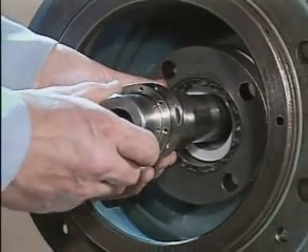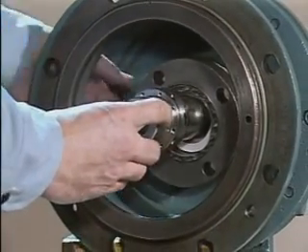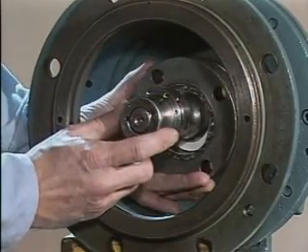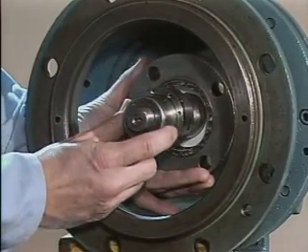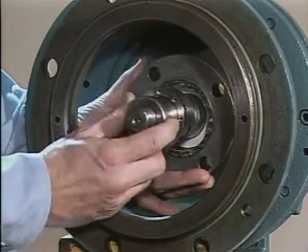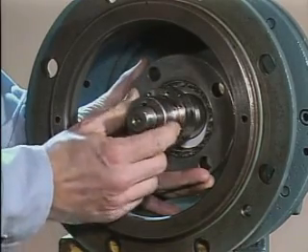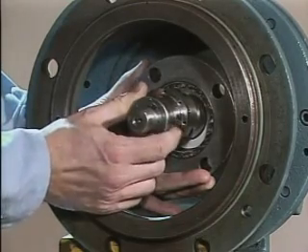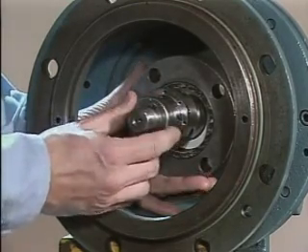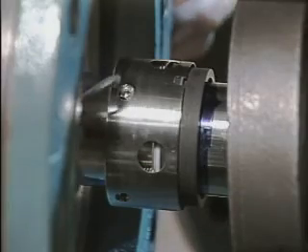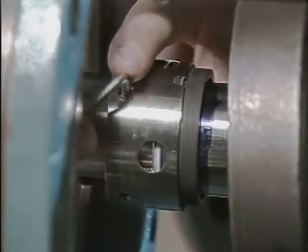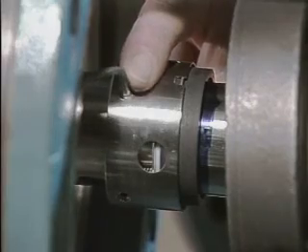Then the shaft sleeve, which has the rotating element mounted on it, is slid onto the shaft. The gland plate should be supported while the sleeve is installed, and the sleeve should be pushed back all the way until it's flush with the shaft shoulder. It's also important to make sure that the keyway on the sleeve lines up with the pin or key on the shaft. The set screws on the rotating element collar, which were only partially tightened earlier, can now be tightened completely.